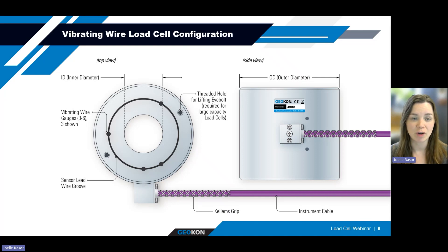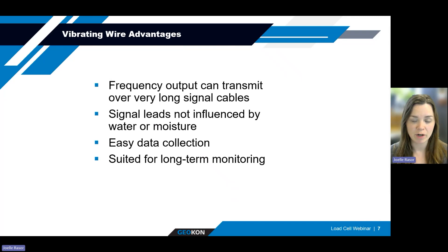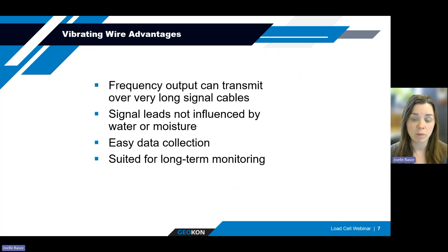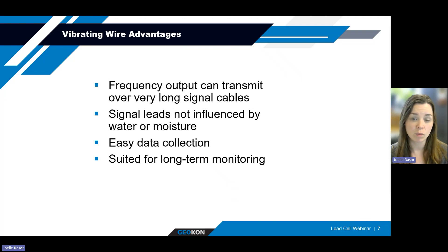Looking at some of the advantages of vibrating wire technology: the frequency output of the vibrating wire can transmit over very long cable lengths without any signal degradation. We've successfully tested our vibrating wire instruments with cable lengths in excess of 3,000 meters without any effect on the output of the gauge. Vibrating wire technology has been available on the market for several decades and has a wide variety of options for data collection, from manual readout boxes all the way through cloud-based data logging systems. It has proven stability over long-term monitoring projects and the ability to continue operating for decades when properly installed and maintained. Vibrating wire load cells are best used for static load monitoring, as dynamic use may not be economically feasible depending on the quantity.